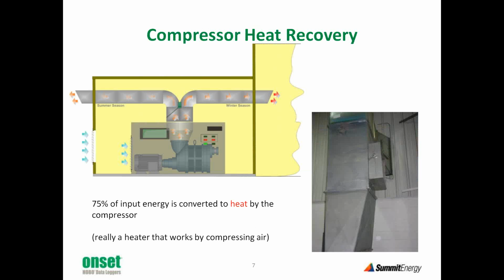Now, a typical heat recovery system might look like this, where we bring outside air in across the air compressor, and then in the summertime we vent it back outside if we don't have a use for it. But in the winter, we vent it into the building. Now, there's a couple of advantages here. One is that the waste heat ends up in the building envelope, but the other is that the outside air is helping to pressurize the building.